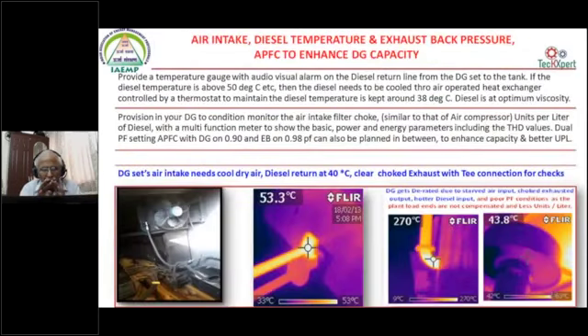So, I'm just covering all the aspects of the utilities. This can be taken to the process machines also. The generator is now not much used, but whichever generator is being used, say once a month for 10 hours or 12 hours, at least see to it that the return diesel temperature is maintained at around 40 degrees. You need to have a heat exchanger, a post air cooler type of heat exchanger, and fit it from the main return line to the diesel tank. Automatically, the temperature will be maintained at 40 degrees.